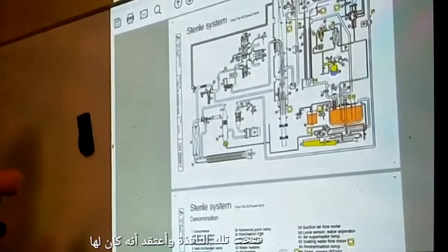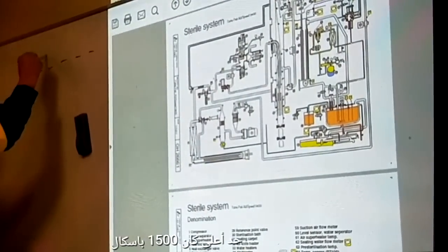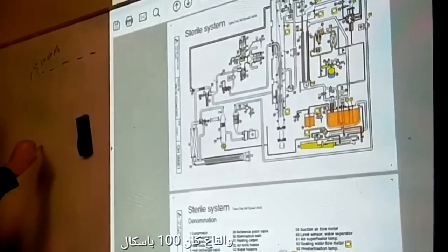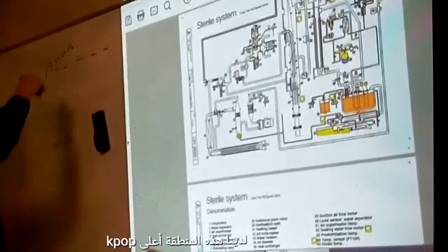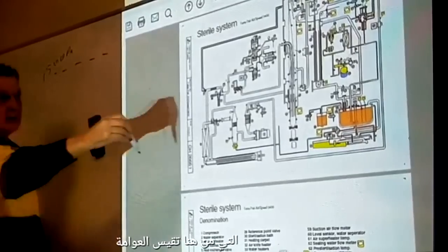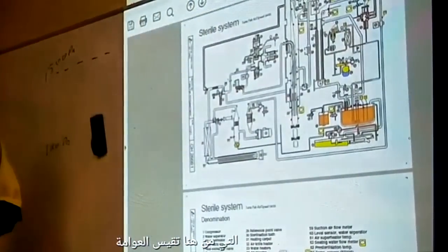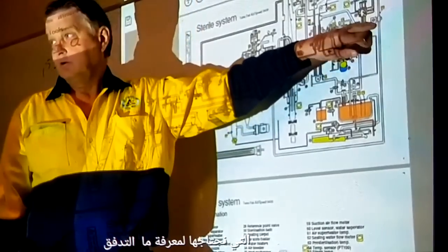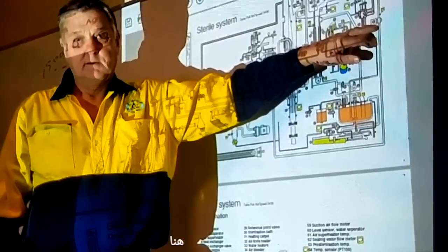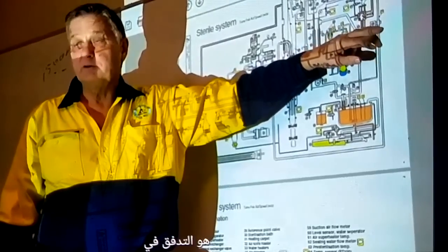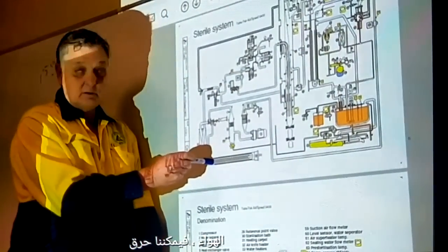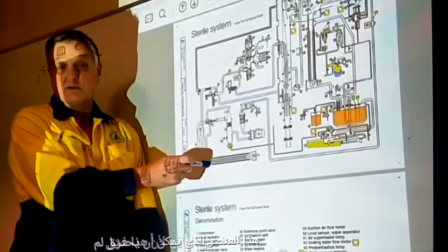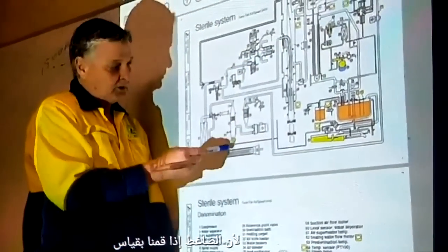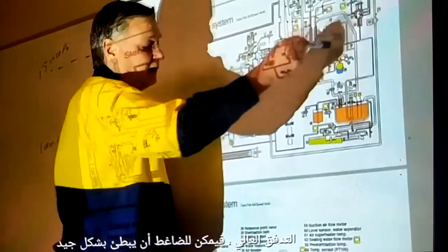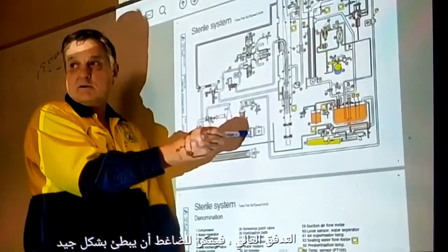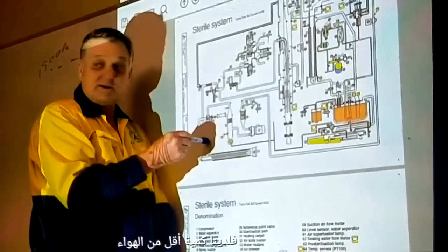Remember I opened up that window, I think the top limit was 1,500 PA, the bottom was 100 PA. We had this area, and I opened up the tip, that's from here, measuring the flow. We need to know what the flow is, because if we don't know what the flow is, we can burn this element out. And it actually is happening because this is slow. Because if we measure high flow, the compressor can slow down. When the compressor slows down, we have less air.